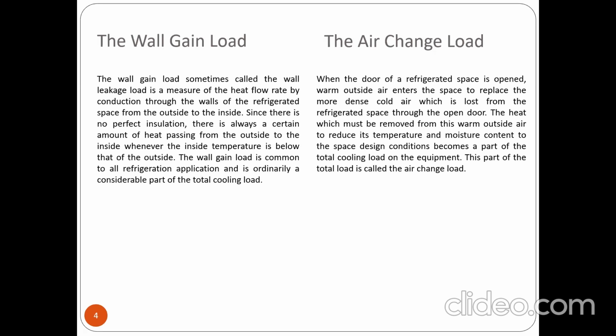Now the air change load. When the door of a refrigerated space is open, warm outside air enters the space to replace the more dense cold air, which is lost from the refrigerated space through the open door. The heat which must be removed from this warm outside air to reduce its temperature and moisture content to the space design condition becomes a part of the total cooling load on the equipment. This part of the total cooling load is the air change load.